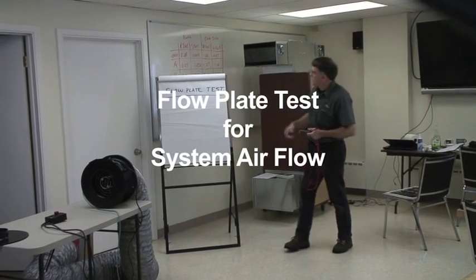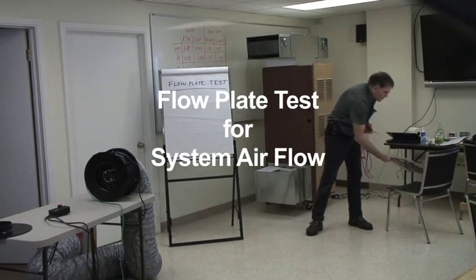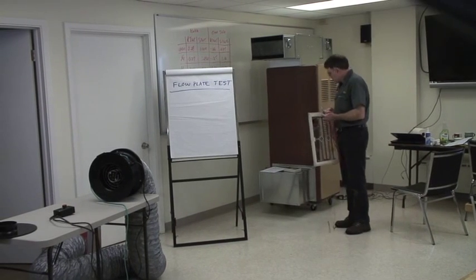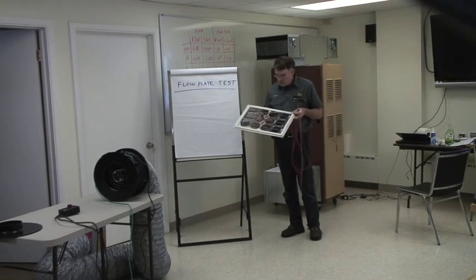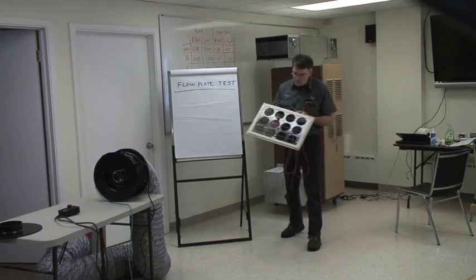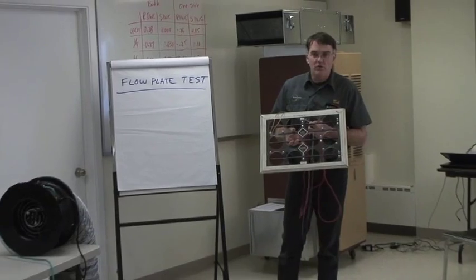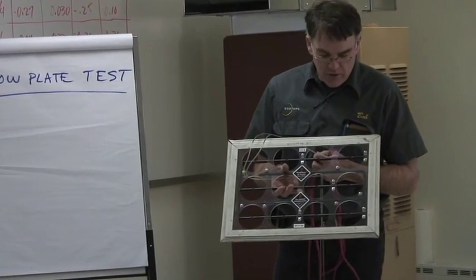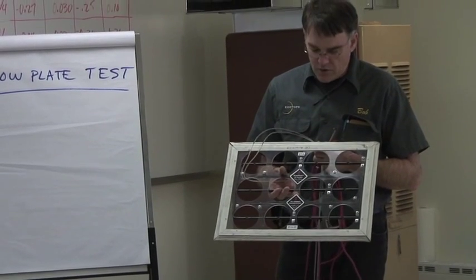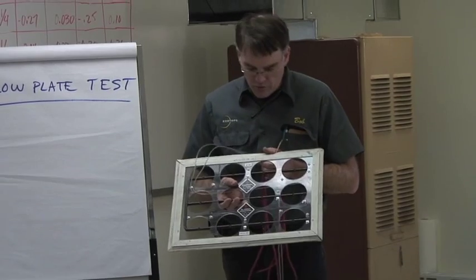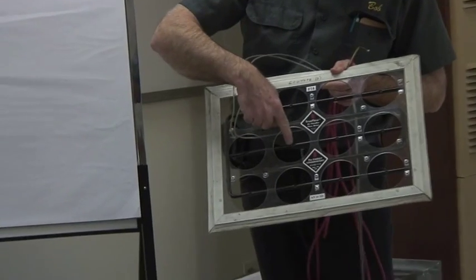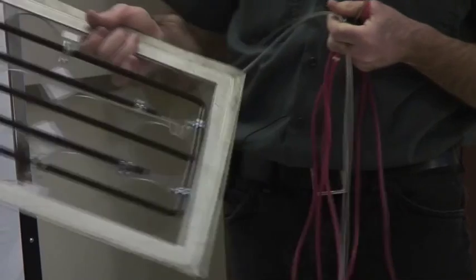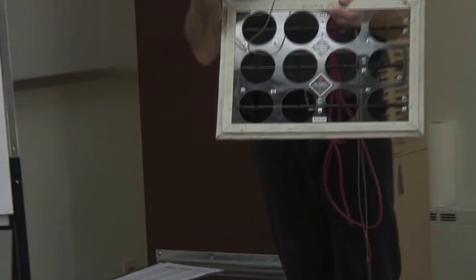The test we're going to perform now is a flow plate test to get system airflow through our central heating and cooling system. Flow plate is a generic name for a device such as this. This is probably the best known, the Energy Conservatory True Flow plate, the smaller of the two plates. This plate works on the principle of air moving across this device. There's holes here with pressure sensing taps on both the front and back. When we hook it up to our pressure gauge, we can convert it into cubic feet per minute or CFM.